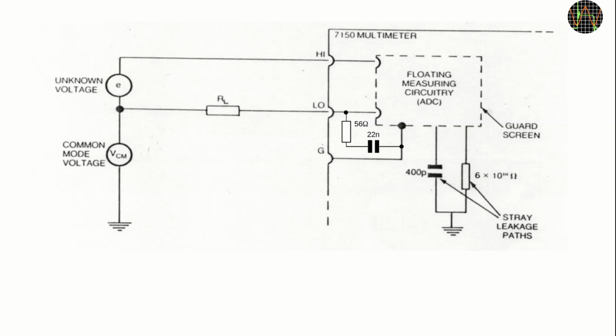This raises the question why modern meters don't have a guard terminal. While connecting an external guard terminal is probably the best way to suppress common mode interference, it's inconvenient to use 3 measurement leads, so they use internal ways to do a similar thing, and that works good enough. Even the Solartron 7150 Plus already has a built-in circuit that consists of an RC network that is adequate for most cases, so you don't have to use the guard terminal. However, these capacitors have a max voltage rating, and this is where one has to pay attention to not damage the multimeter when high voltages are involved.